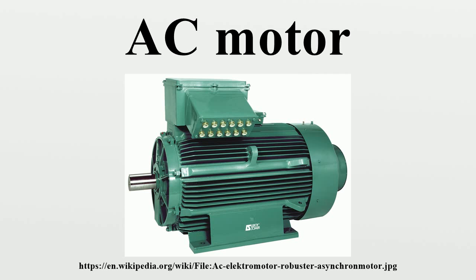The two main types of AC motors are classified as induction and synchronous. The induction motor always relies on a small difference in speed between the stator rotating magnetic field and the rotor shaft speed, called slip, to induce rotor current in the rotor AC winding. As a result, the induction motor cannot produce torque near synchronous speed where induction is irrelevant or ceases to exist.